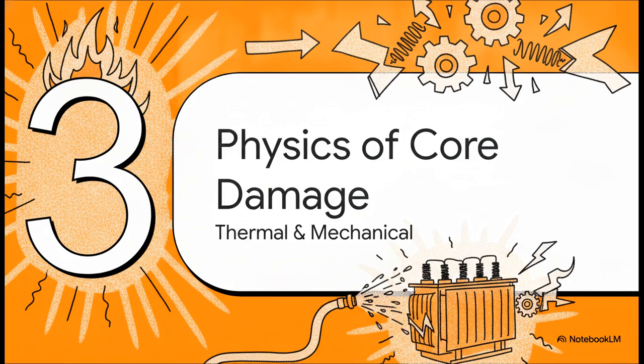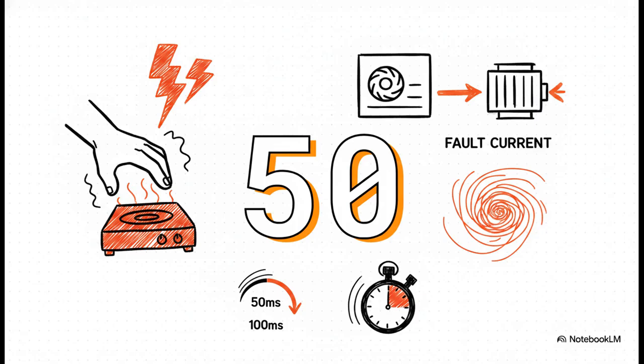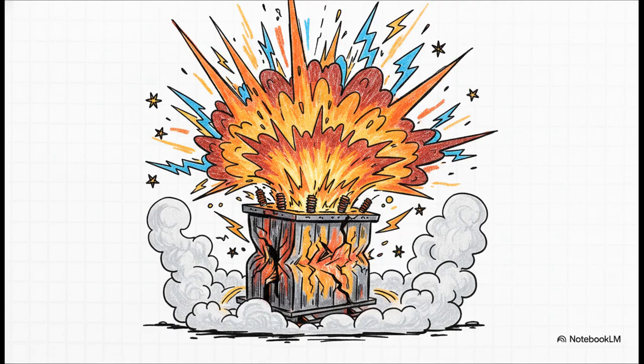So what does this actually mean for the hardware? Section 3, Physics of Core Damage. We engineers often obsess over whether a relay tripped, but the physical equipment only cares about how many milliseconds passed before the interruption. Think about touching a hot stove. Pulling your hand away instantly versus, say, a half second later makes an enormous difference in the burn you get, even though both feel fast to us. It's the exact same for a transformer core. A fault cleared in 50 milliseconds delivers roughly half the thermal energy of a 100-millisecond fault. Why? Because energy scales with time at constant current squared. Every single millisecond that the generator continues to feed the fault is just compounding the thermal and mechanical stress on your equipment. If we don't shut down both of those sources instantly, the escalation is absolutely brutal.